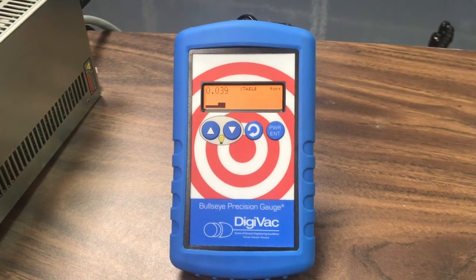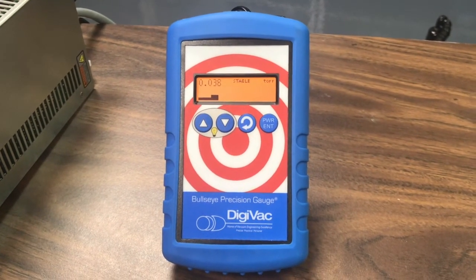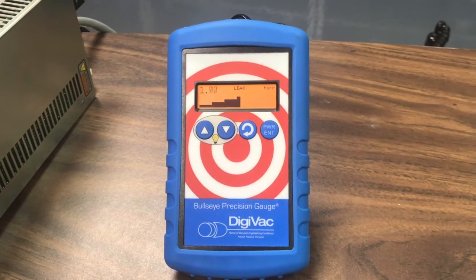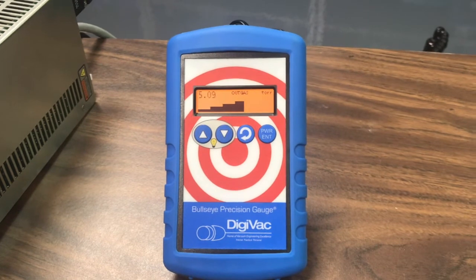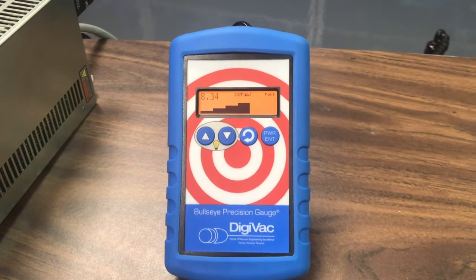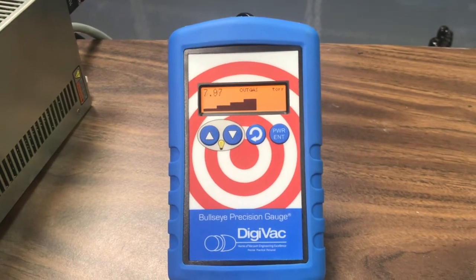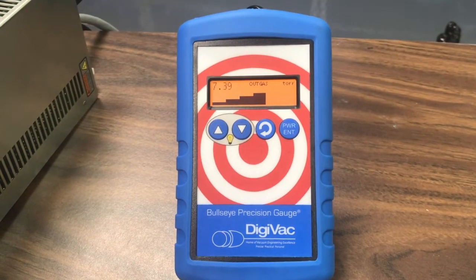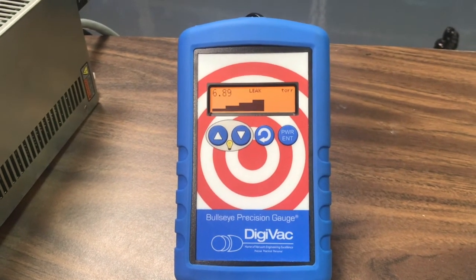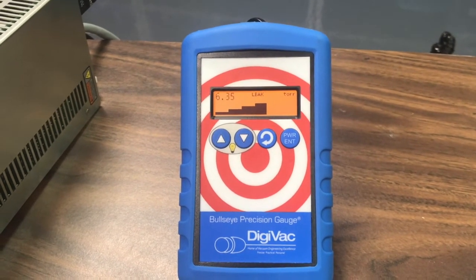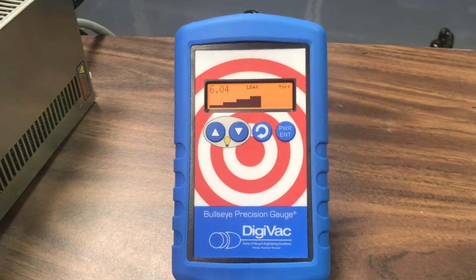You just keep focusing on that gauge. What will happen is I just pulled a vent to the system, right? It was a vent to the system, then I quickly roughed it out. And so what happened is, oh, it actually turned to say outgas. It did. And in this case, what it really meant to say is, hey, uh-oh, the vacuum pressure went up. There was a leak on the system, but you meant to do that.